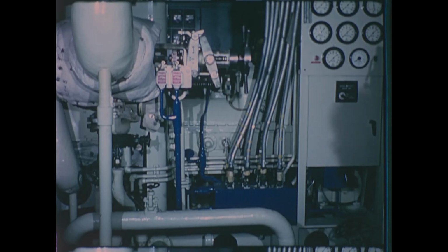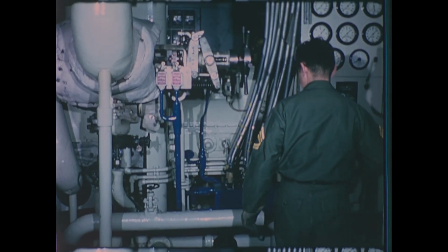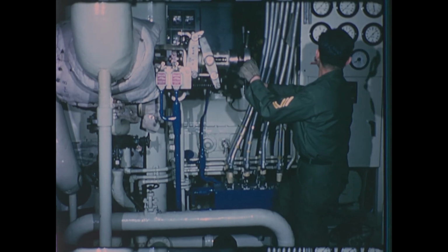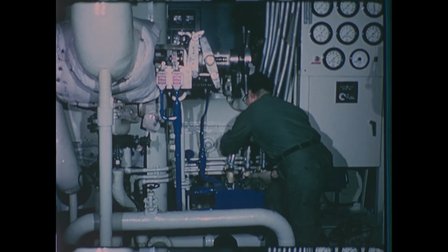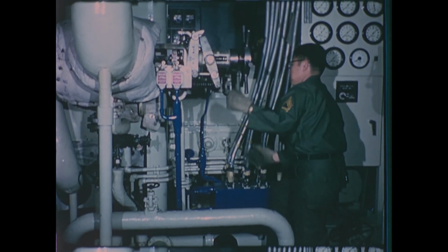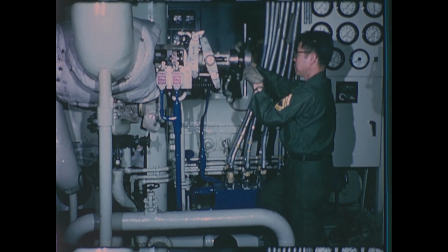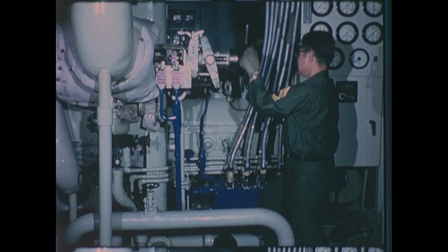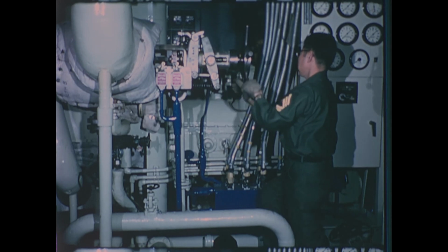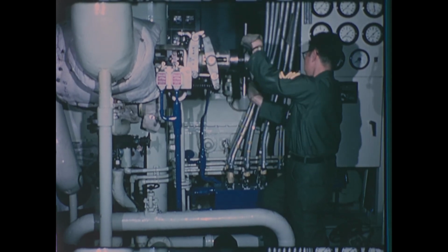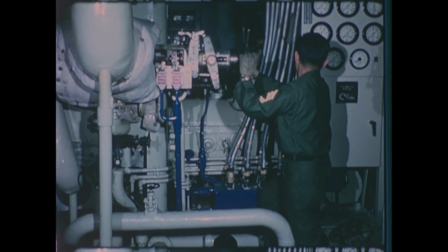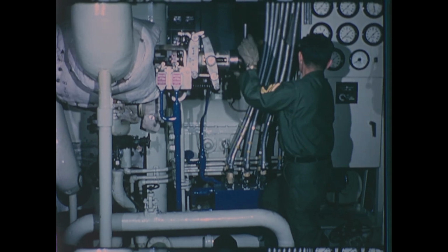Before admitting steam to the turbine, the throttle must be fully closed and the overspeed trip reset. Next, the operator opens the throttle slowly until the rotor is turning. Next, he closes the throttle valve.